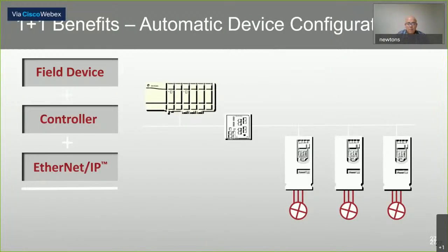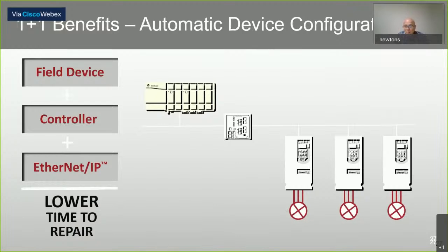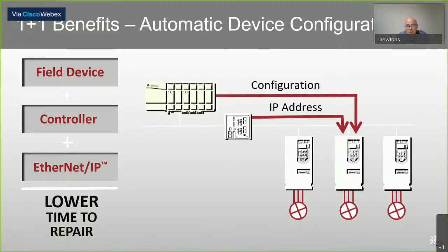The next benefit shown here of the Premier integration is from an operational standpoint, how it helps us in the field from a maintenance and support standpoint. We see here we've got the drives connected to Ethernet, to the Stratix switch, and onto the Logix, similar to what we saw in the earlier slide. In the unlikely event that we lose a drive, it's simply replaced with the appropriate lockout tagout procedures. And then the Stratix switch has got the DHCP port persistence, which will push an IP address to that drive. This will be the same IP address that was on the old drive that has just failed and been replaced.